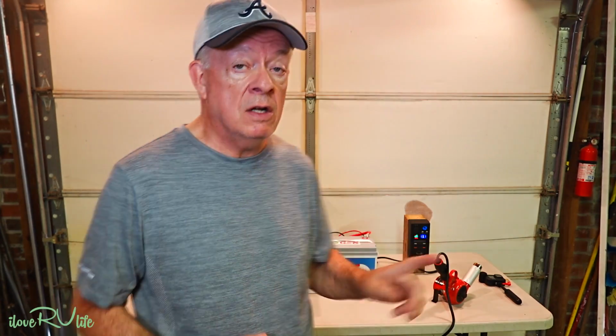So I was showing you how I could use the 1,000 watts. What I want to show you now is what happens if you overload it. I'm going to overload this battery because I want to see the BMS shut off when I go over 100 amps, using a heat gun that pulls about 1,650 watts. That should push this battery up to somewhere around 140 to 150 amps, and the battery management system will shut off. I can assure you of that, even though I haven't done it yet. It'll probably take 3 or 4 seconds because it can handle a surge, but once it determines this is long term and not a surge, it'll shut off.